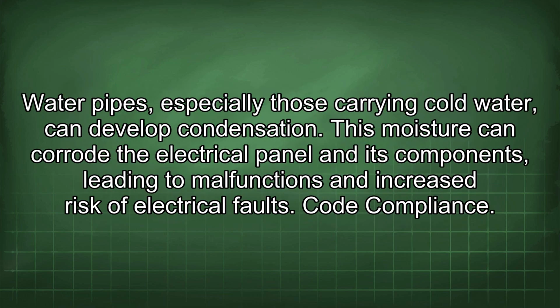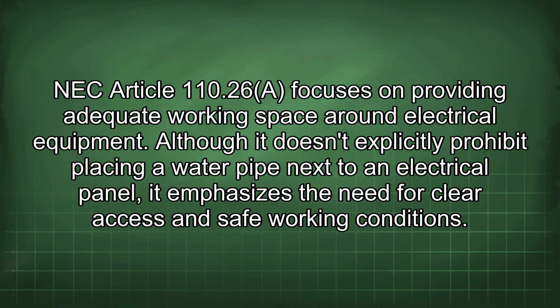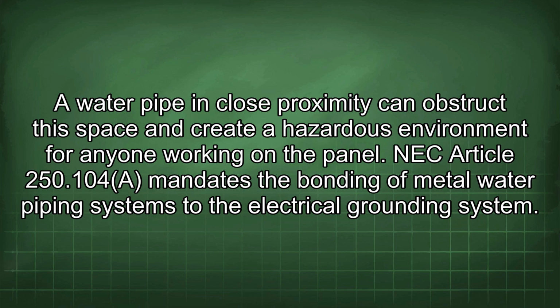Corrosion and moisture. Water pipes, especially those carrying cold water, can develop condensation. This moisture can corrode the electrical panel and its components, leading to malfunctions and increased risk of electrical faults. Code compliance. NEC Article 110.26 focuses on providing adequate working space around electrical equipment. Although it doesn't explicitly prohibit placing a water pipe next to an electrical panel, it emphasizes the need for clear access and safe working conditions. A water pipe in close proximity can obstruct this space and create a hazardous environment for anyone working on the panel.